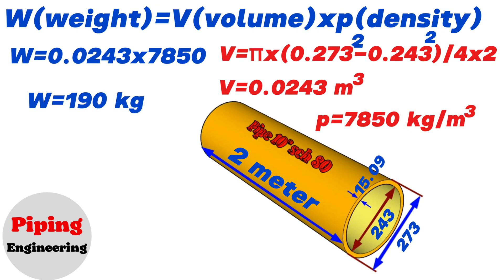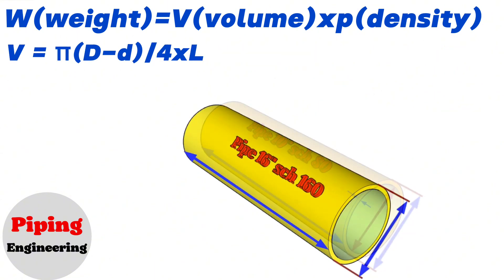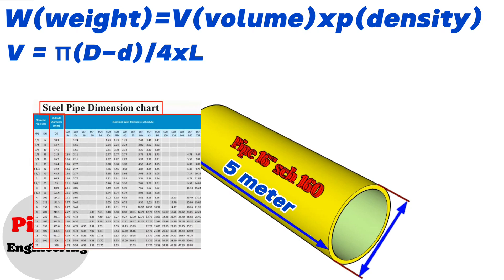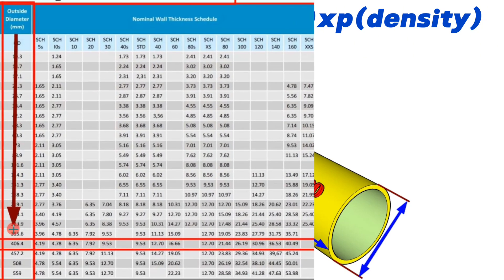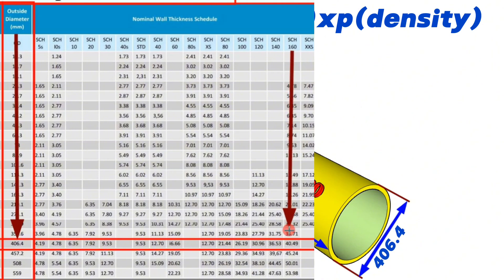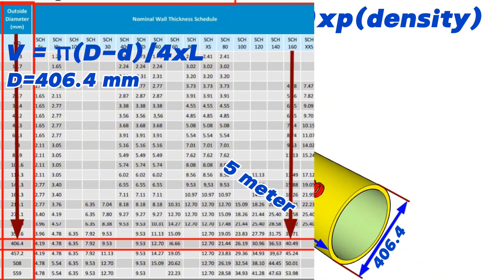Now let's calculate the weight of a 16 inch iron pipe with a wall thickness of schedule 160 and a length of 5 meters. Since we already know the calculation steps, we will move quickly. Looking at the row for nominal pipe size 16 inch in the pipe size chart, we find that the outer diameter of the 16 inch schedule 160 pipe is 406.4 millimeters and the wall thickness is 40.49 millimeters.